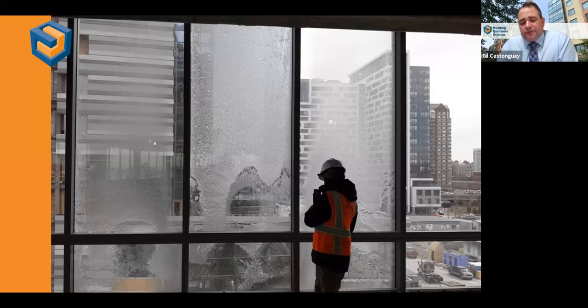The testing ended up going off anyway. It actually provided an opportunity to see how some of these systems perform with ice accumulation, but you also have to account for that in your test report, giving a statement as to whether or not the testing was affected, and so forth. So be aware this is a logistical issue, you have to look at weather way in advance. What time of year are you planning this testing? Make sure that's accounted for in your testing plan. Even when writing the spec, you should be thinking about the schedule way in advance, as to when the project may be constructed and what type of testing is feasible.